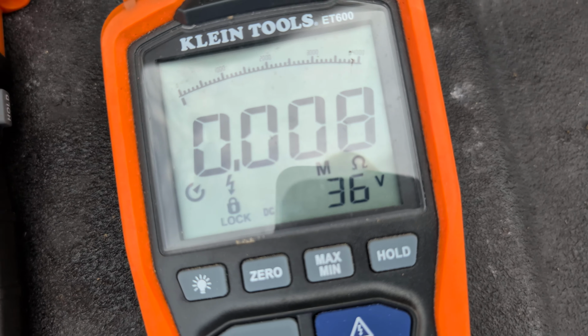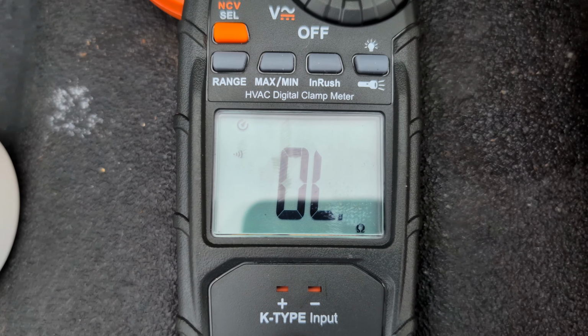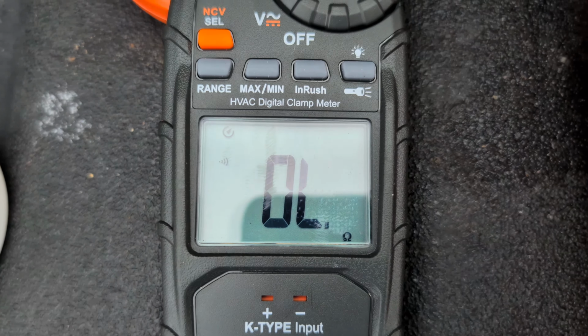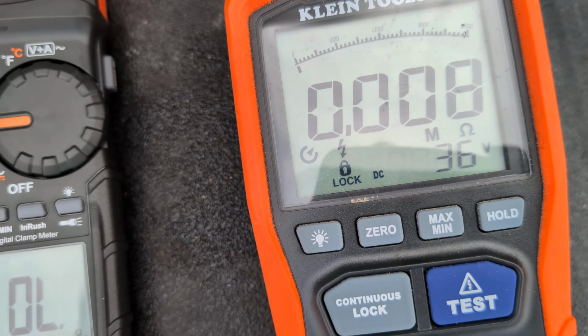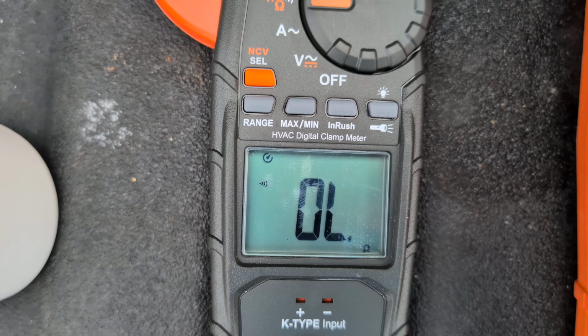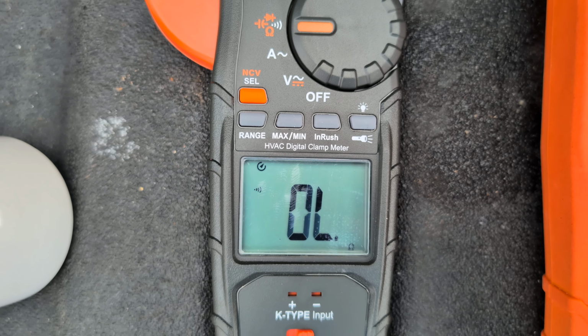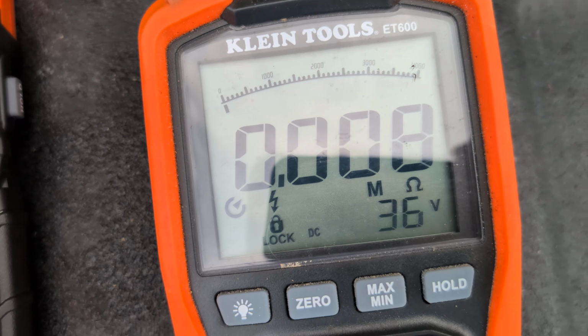This is why you need a megohm meter, because with this normal continuity tester, both of them measure ohms. This one measures ohms by putting a 3 to 9 volt battery onto the circuit. This one measures ohms by pumping up the voltage with special circuitry to 125 volts to simulate a realistic condition. And under that realistic condition, we can see there's a fault.